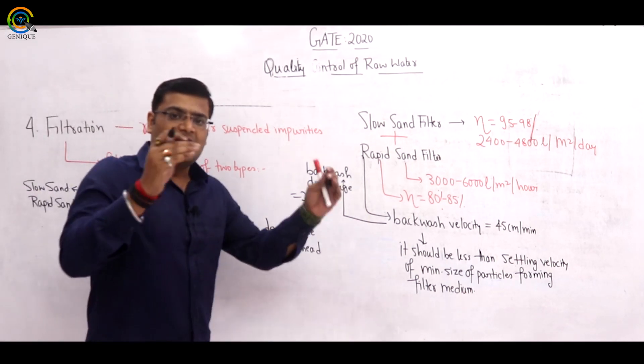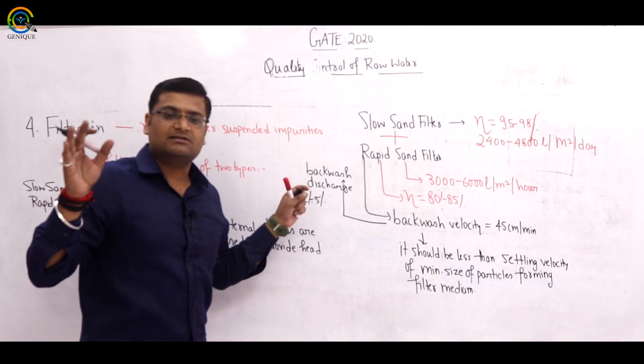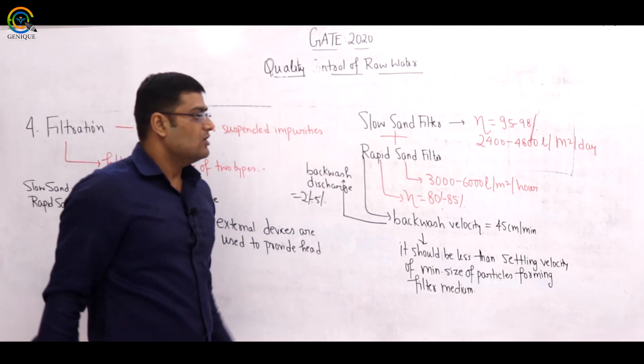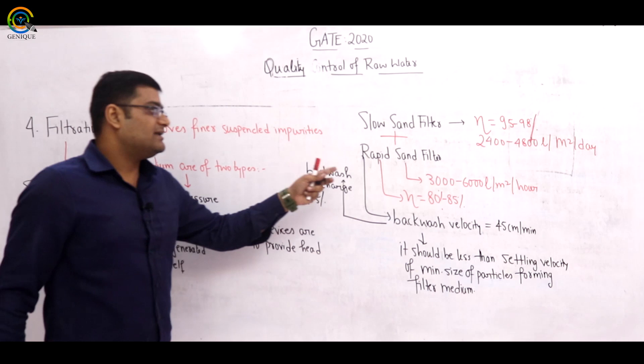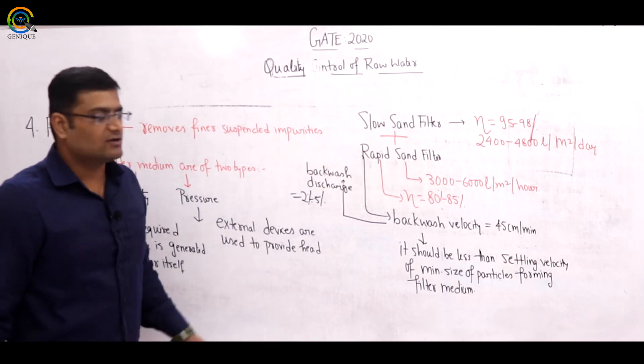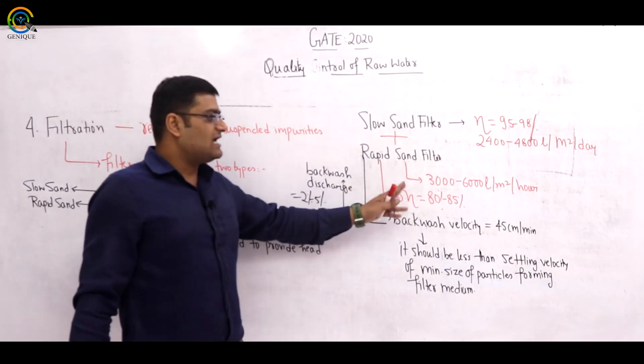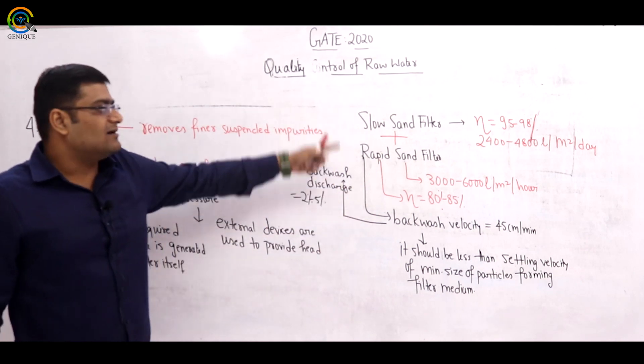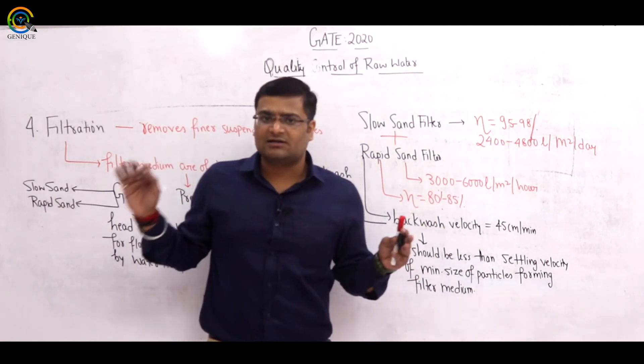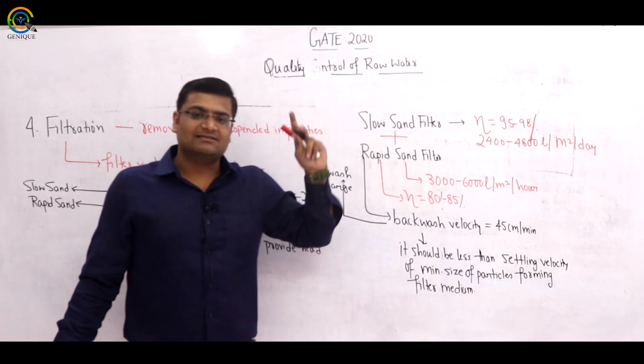Comparing cleaning methods: in slow sand filter, 10–15 mm of sand is removed, particles cleared, and the layer restored — a time-consuming and tedious process. But in rapid sand filter, the cleaning period is only 30 minutes. Rate is high, but efficiency is less compared to slow sand filter. For a small amount of water, always go for slow sand filter.